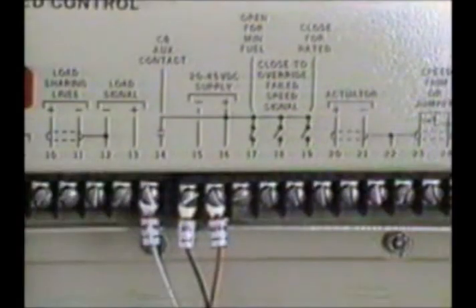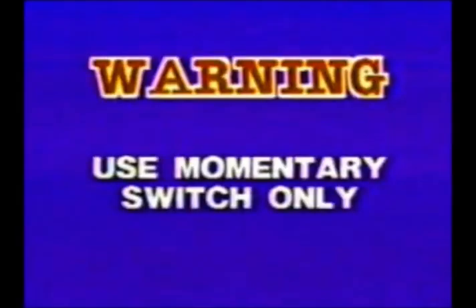Terminal 18 now is our close to override failed speed signal. I again have a switch in my switchgear for that. Now, that is a momentary switch. You only want a momentary switch for your close to override failed speed signal.